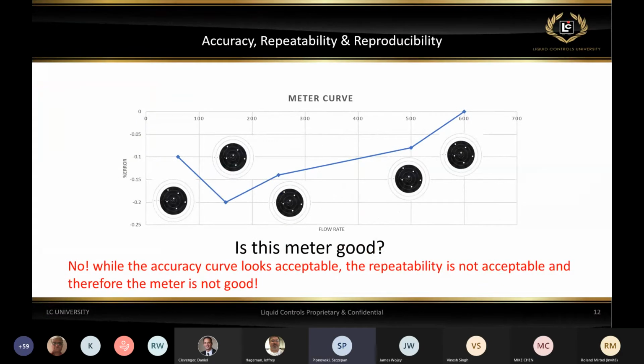Now, this is another curve of a meter. Again, if you look at overall linearity, it's pretty good. It's at 0.2%. But if you look at the repeatability of that meter at all the points, that repeatability is not there. That meter is not acceptable. This meter is not acceptable because of its repeatability. A meter cannot be considered accurate if it's not repeatable.